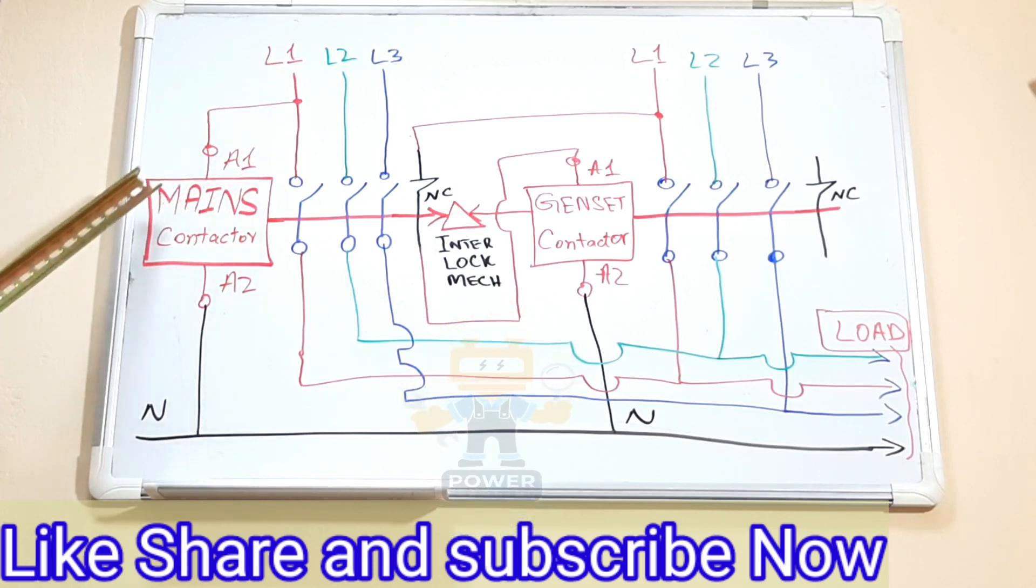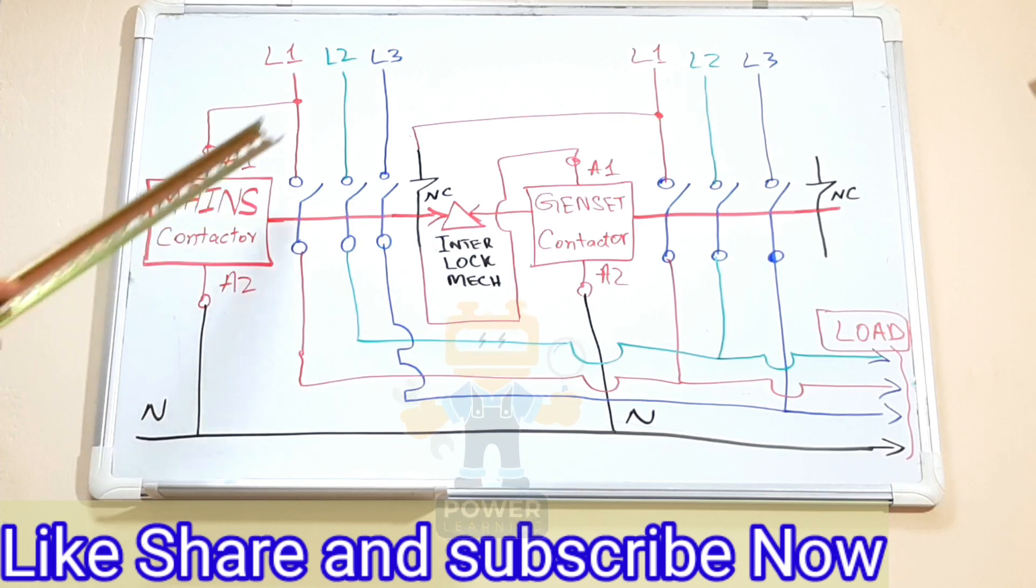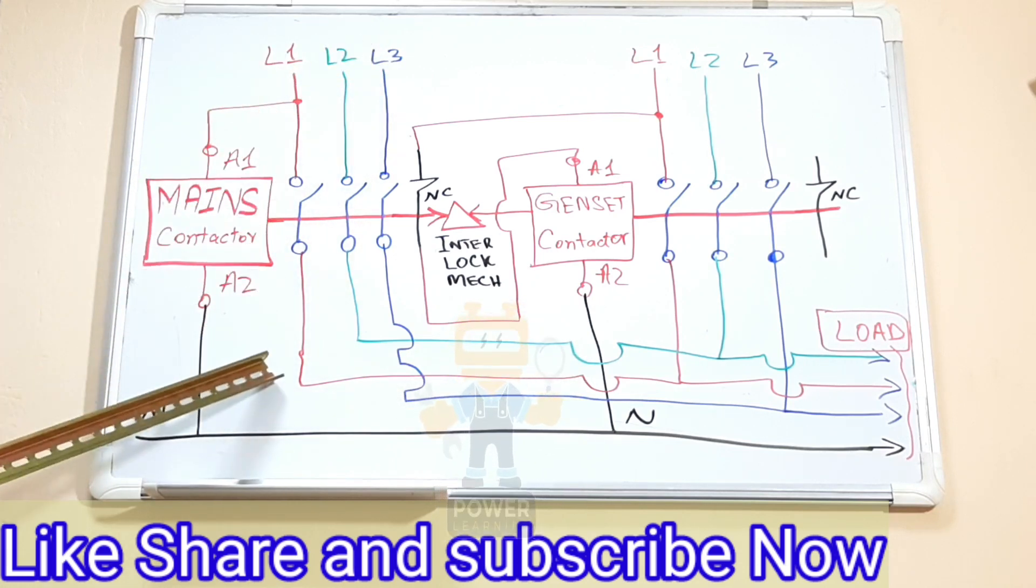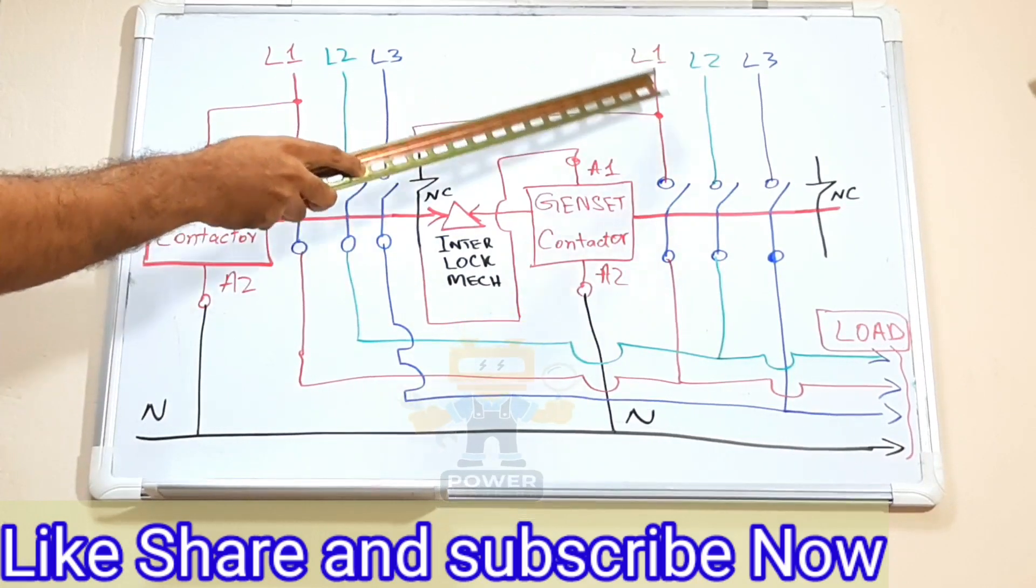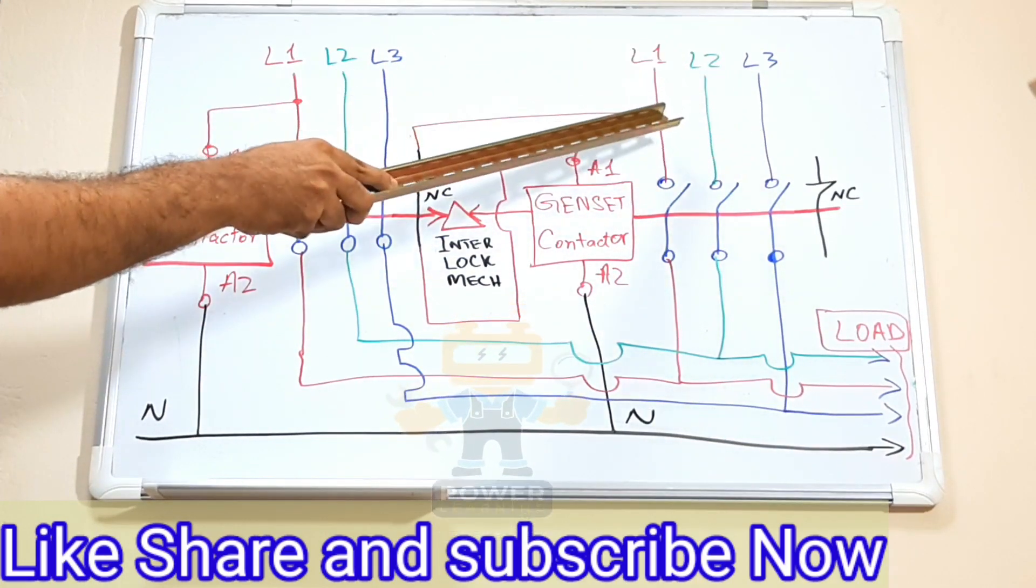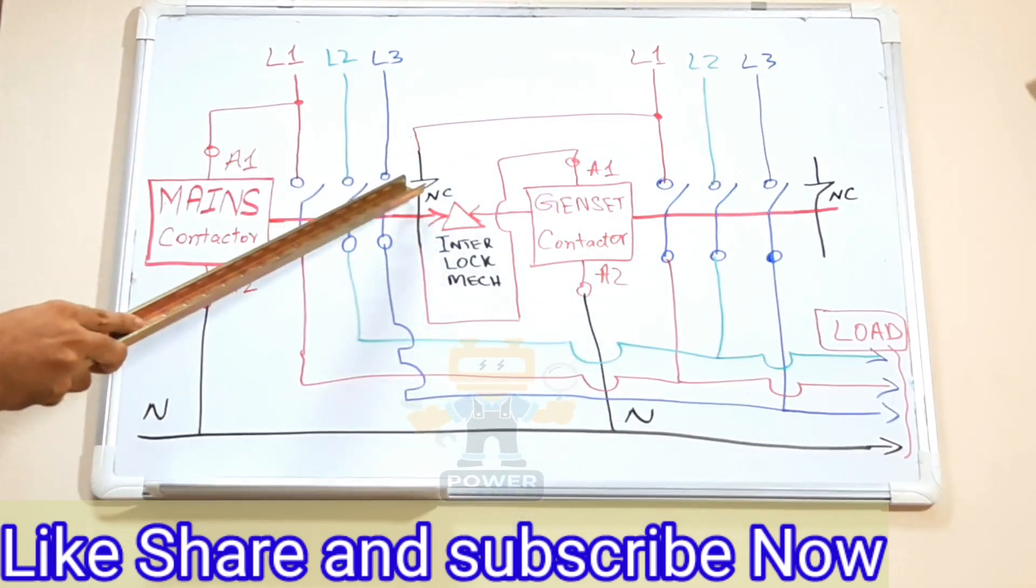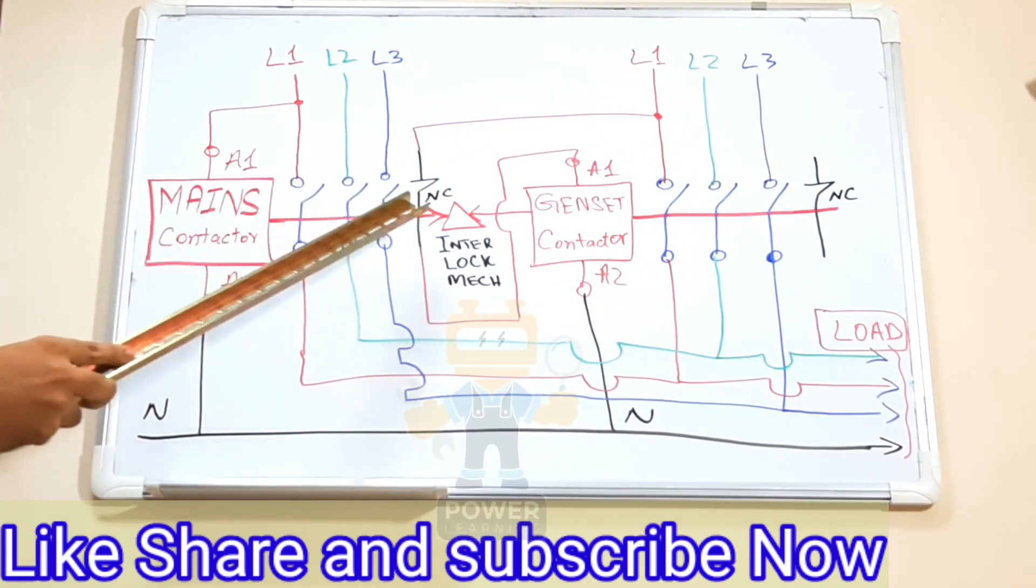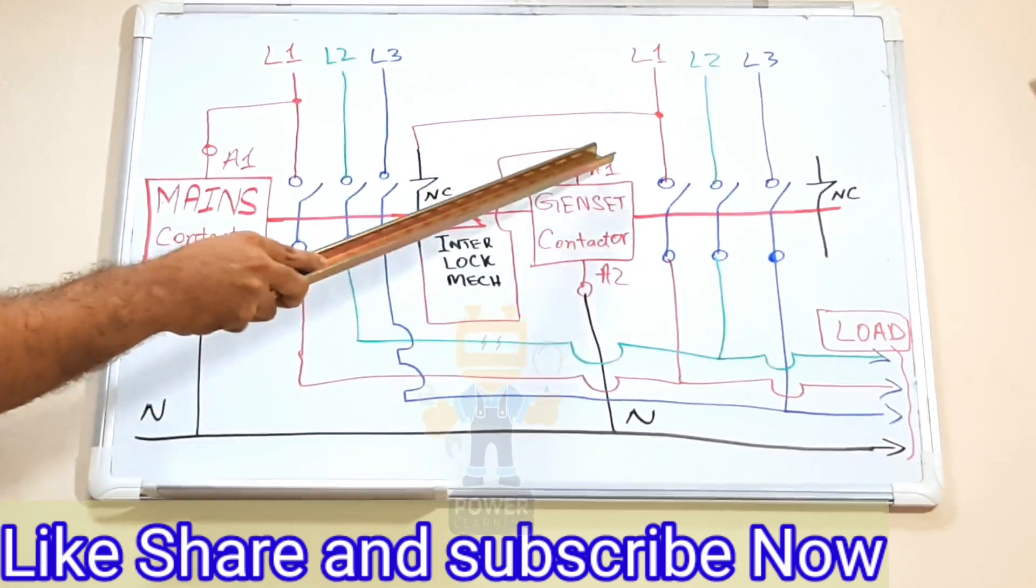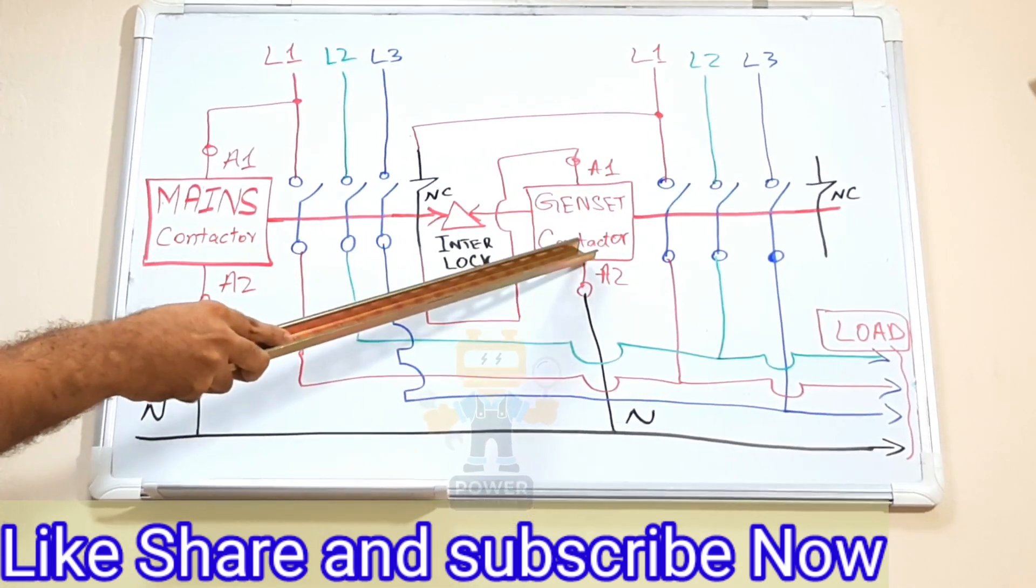When the power is available this will be energized directly. Neutral is connected here, our three phases are connected here and going towards the load. Here what I do, this is generator three lines. I will take one phase from generator, bring it through normally closed auxiliary contact of mains, then I take it back to the coil of genset contactor.